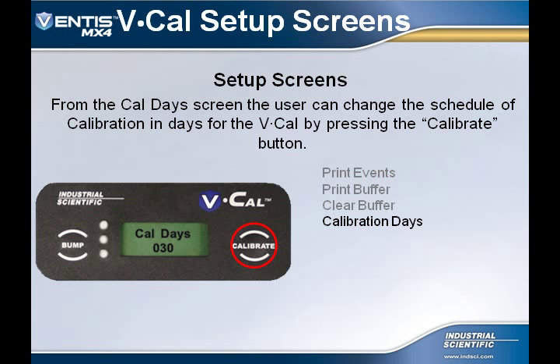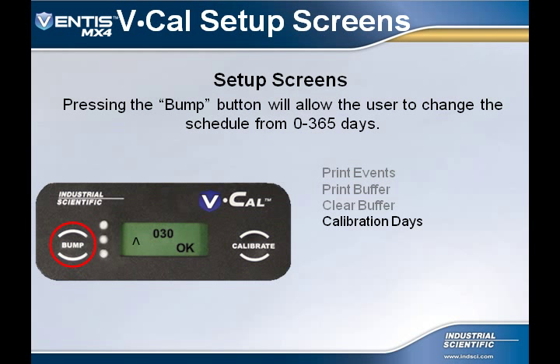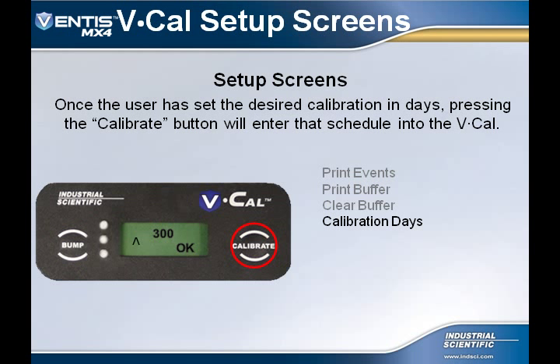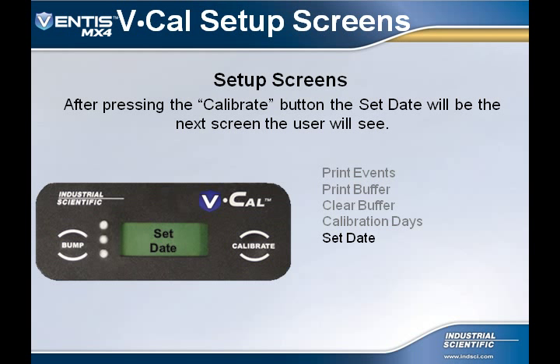This option allows the user to change the schedule of calibration in days for the VCal by pressing the calibration button. Pressing the bump button allows the user to schedule the calibration in days from 0 to 365. Here the calibration in days has been set to 300. Pressing the calibrate button will enter that schedule into the VCal. The next option is Set Date screen. This allows the user to set the correct date in the VCal.